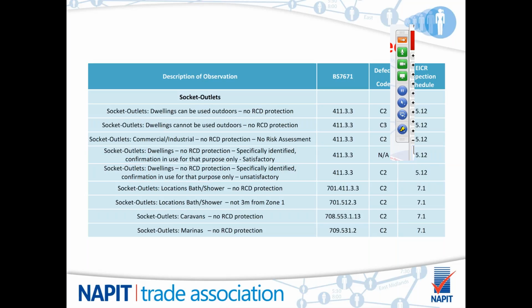Other areas, dwellings, no RCD protection, but we have a specifically identified piece of equipment. Again, we would need to make sure that it was just for that piece of equipment and no other. If it's just used for a particular piece of equipment, satisfactory, and if it's used for other things, C2, because it's inherently dangerous. Within bathrooms, rooms containing baths and showers, if there are socket outlets with no RCD, it's going to have to be a C2.